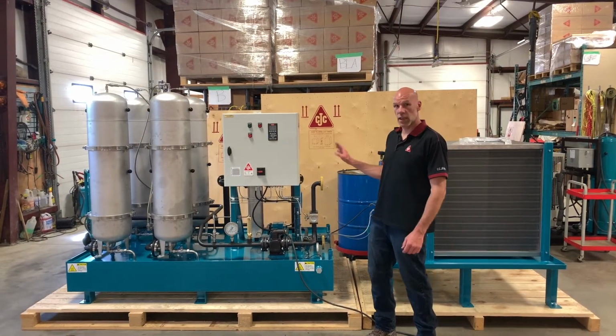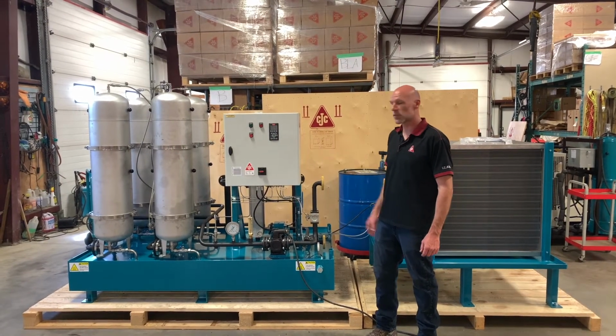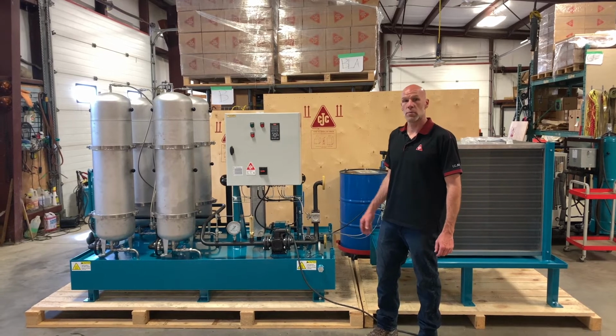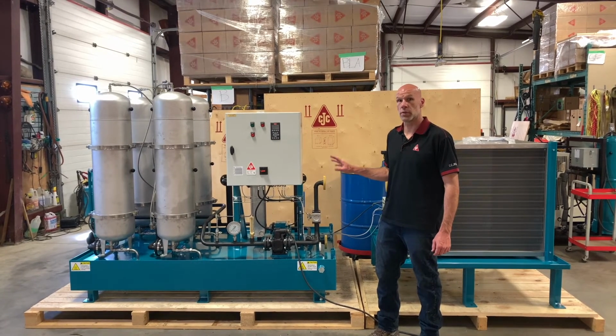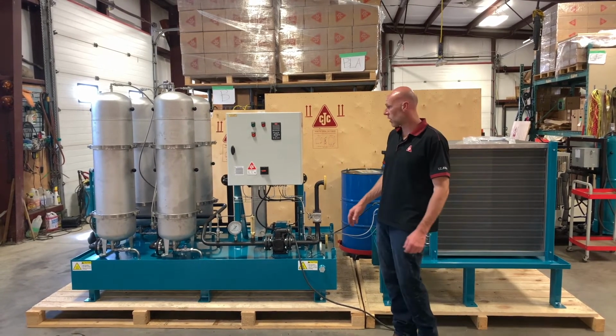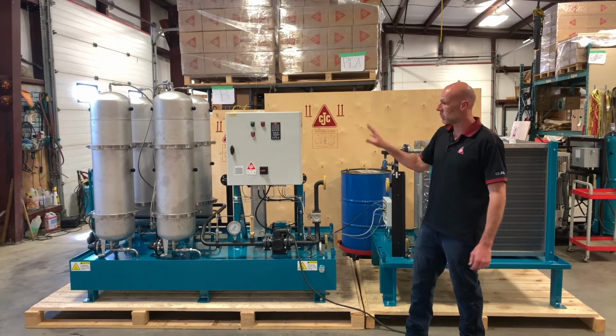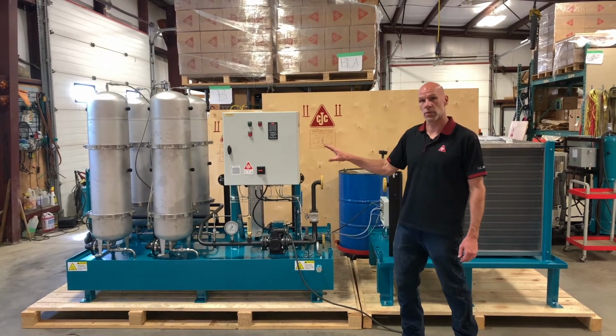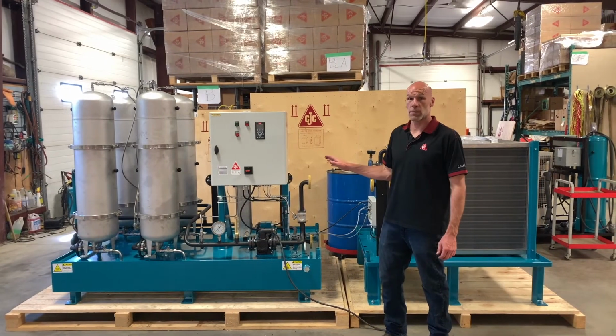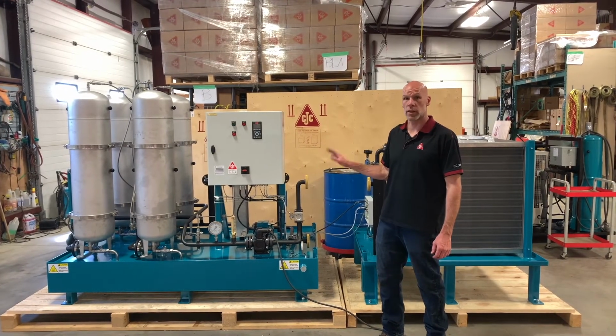The C.C.Jensen HTO thermal oil filtration system is a very effective way of maintaining the fluid properties of your thermal oil systems. The combination of cooling skid plus the high density fine filtration media makes it a very effective package to maintain your oil in optimum condition.